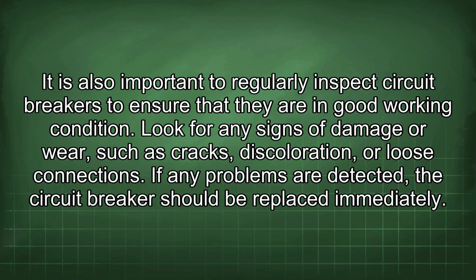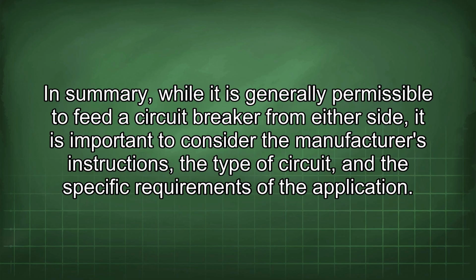It is also important to regularly inspect circuit breakers to ensure that they are in good working condition. Look for any signs of damage or wear, such as cracks, discoloration, or loose connections. If any problems are detected, the circuit breaker should be replaced immediately. In summary, while it is generally permissible to feed a circuit breaker from either side, it is important to consider the manufacturer's instructions, the type of circuit, and the specific requirements of the application.